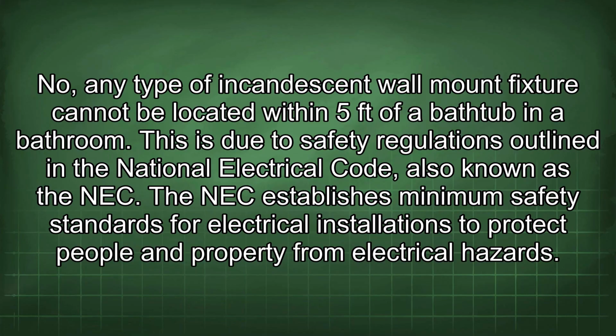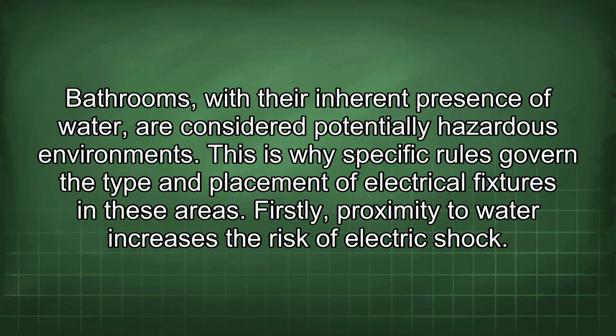No, any type of incandescent wall mount fixture cannot be located within 5 ft of a bathtub in a bathroom. This is due to safety regulations outlined in the National Electrical Code, also known as the NEC. The NEC establishes minimum safety standards for electrical installations to protect people and property from electrical hazard. Bathrooms, with their inherent presence of water, are considered potentially hazardous environments. This is why specific rules govern the type and placement of electrical fixtures in these areas.